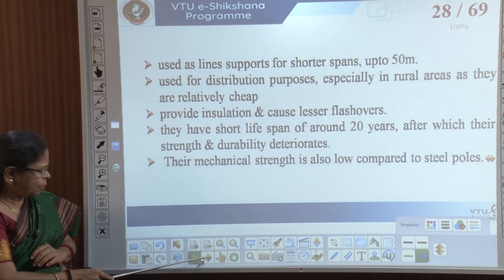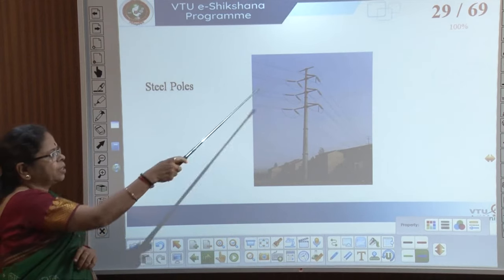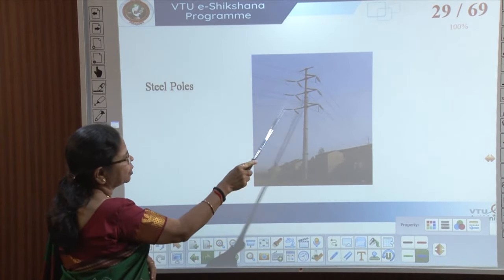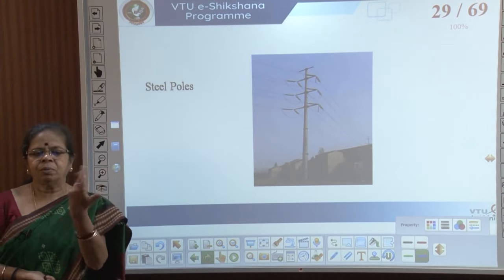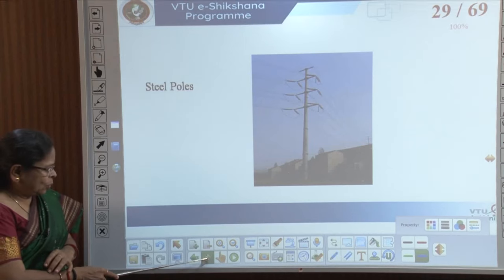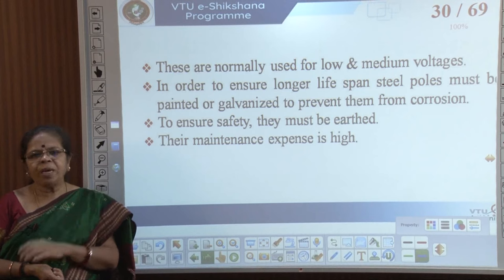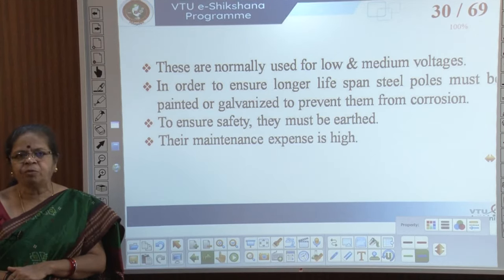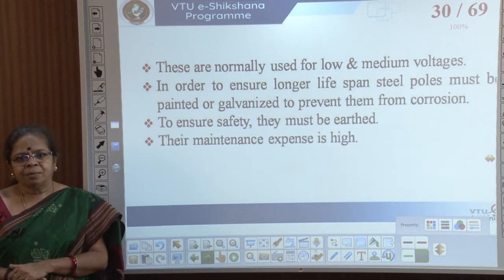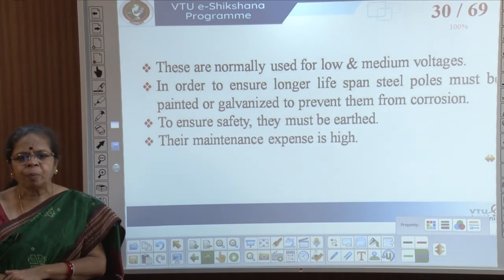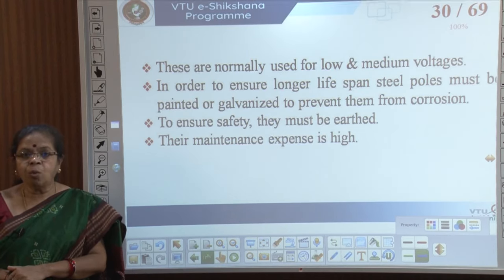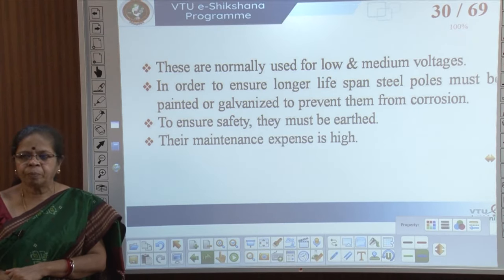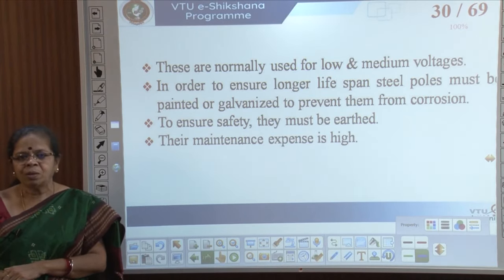Steel poles are used for medium and low voltages. They have a longer lifespan because you can protect them from weather by galvanizing, which prevents corrosion. However, steel is a conductor unlike wood, so you have to properly earth the poles. Their maintenance expense is higher, but their lifespan and reliability are greater.